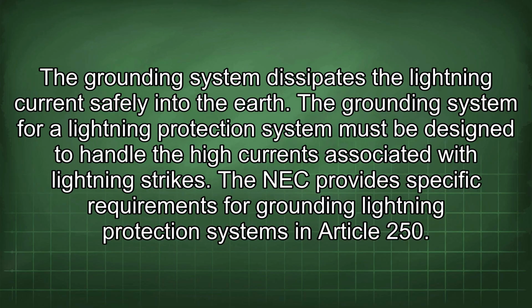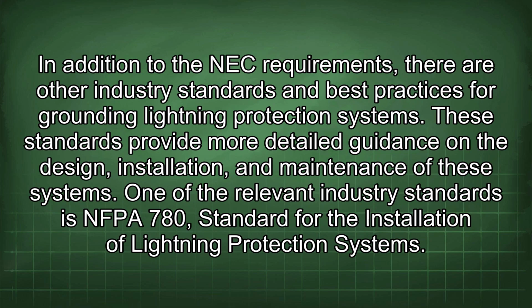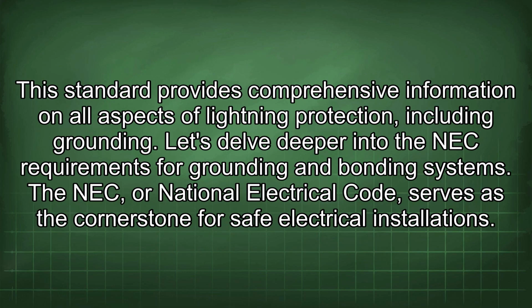The grounding system for a lightning protection system must be designed to handle the high currents associated with lightning strikes. The NEC provides specific requirements for grounding lightning protection systems in Article 250. In addition to the NEC requirements, there are other industry standards and best practices for grounding lightning protection systems. These standards provide more detailed guidance on the design, installation, and maintenance of these systems. One of the relevant industry standards is NFPA 780, Standard for the Installation of Lightning Protection Systems. This standard provides comprehensive information on all aspects of lightning protection, including grounding.